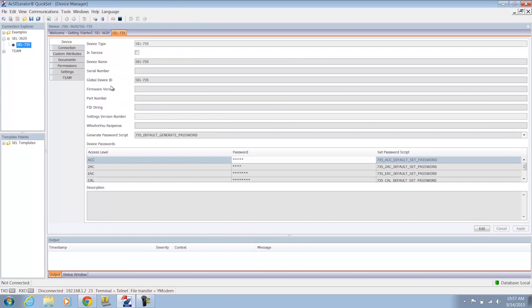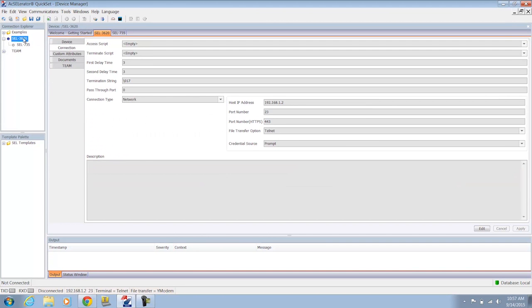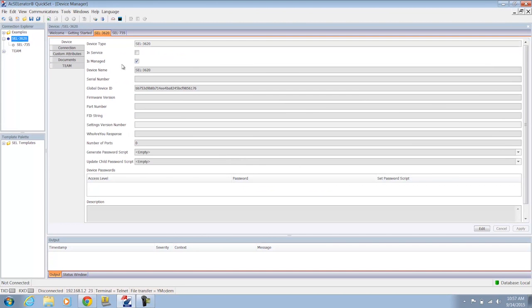I'm going to open up my SEL 735 and then I'll click the permissions tab. Now this permissions tab is not going to show up unless the SEL relay is actually below in that tree, the connection directory tree, the SEL 3620. And the SEL 3620 has its is managed checkbox checked.